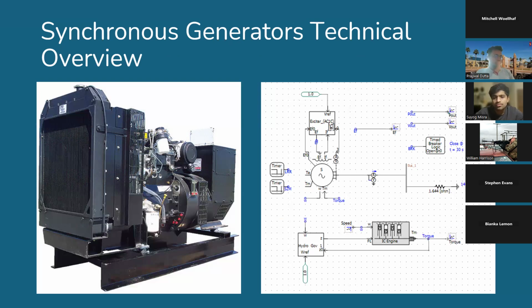In PSCAD, these generators are modeled using a combination of electrical and mechanical equations. The software simulates stator and rotor dynamics, magnetic field interactions, and mechanical inertia to replicate real-world behavior. There are some pre-configured models for synchronous generators, which we have utilized, parameterizing them to how the system would need to fit. One of the key components of a synchronous generator simulation is the exciter, which I'll show on the next slide here. The exciter is responsible for regulating the field current supplied to the rotor, which in turn controls the terminal voltage of the generator.